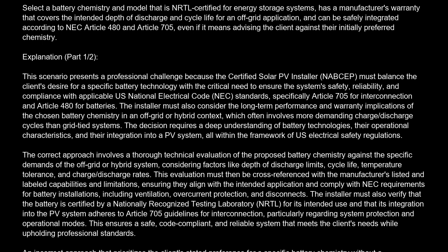This evaluation must then be cross-referenced with the manufacturer's listed and labeled capabilities and limitations, ensuring they align with the intended application and comply with NEC requirements for battery installations, including ventilation, overcurrent protection, and disconnects. The installer must also verify that the battery is certified by a nationally recognized testing laboratory, NRTL, for its intended use, and that its integration into the PV system adheres to Article 705 guidelines for interconnection, particularly regarding system protection and operational modes. This ensures a safe, code-compliant, and reliable system that meets the client's needs while upholding professional standards.